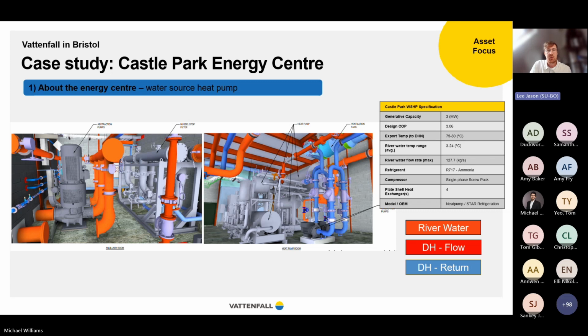A little focus on the energy centre itself: Castle Park Energy Centre and the heat pump is primarily a heating plant. Our OEM for the install was Star Refrigeration, who are also the primary stakeholder helping us maintain and look after the assets. It's a 3 megawatt single compressor water source heat pump, primarily using ammonia as the refrigerant, with a designed coefficient of performance of 3.06.